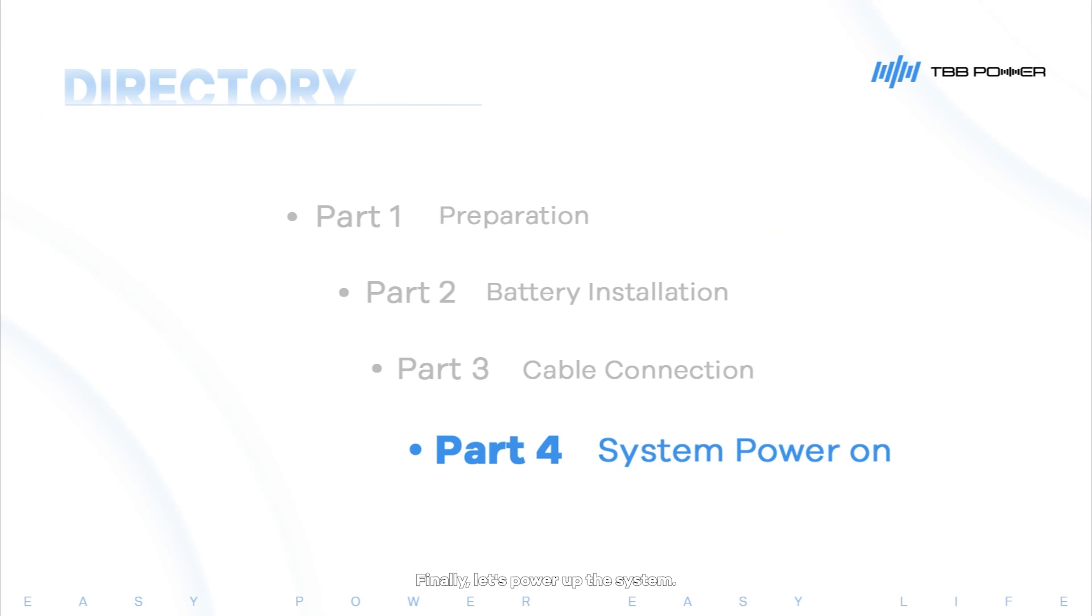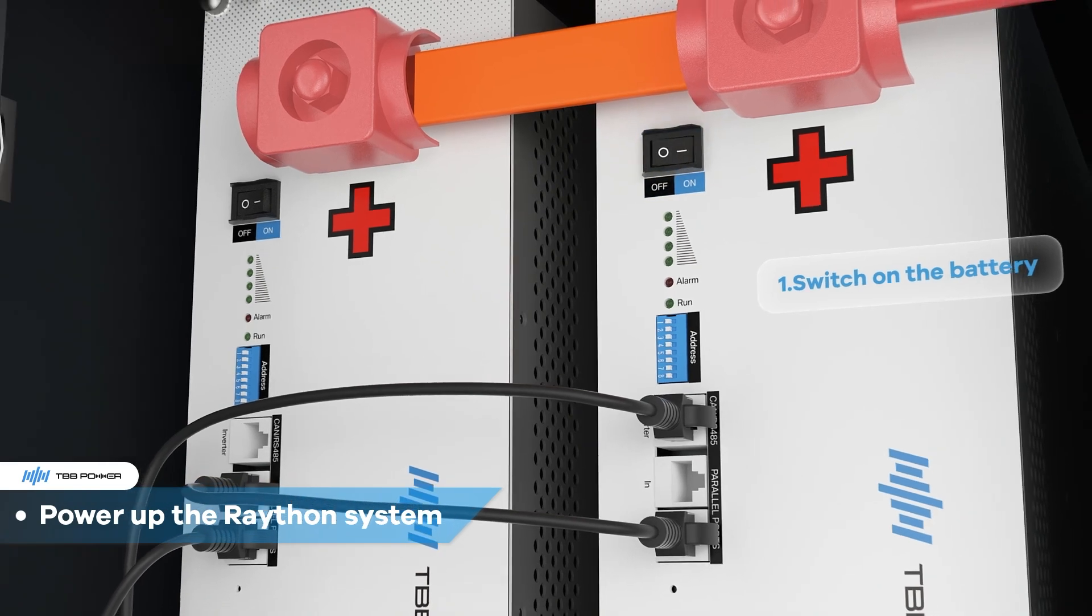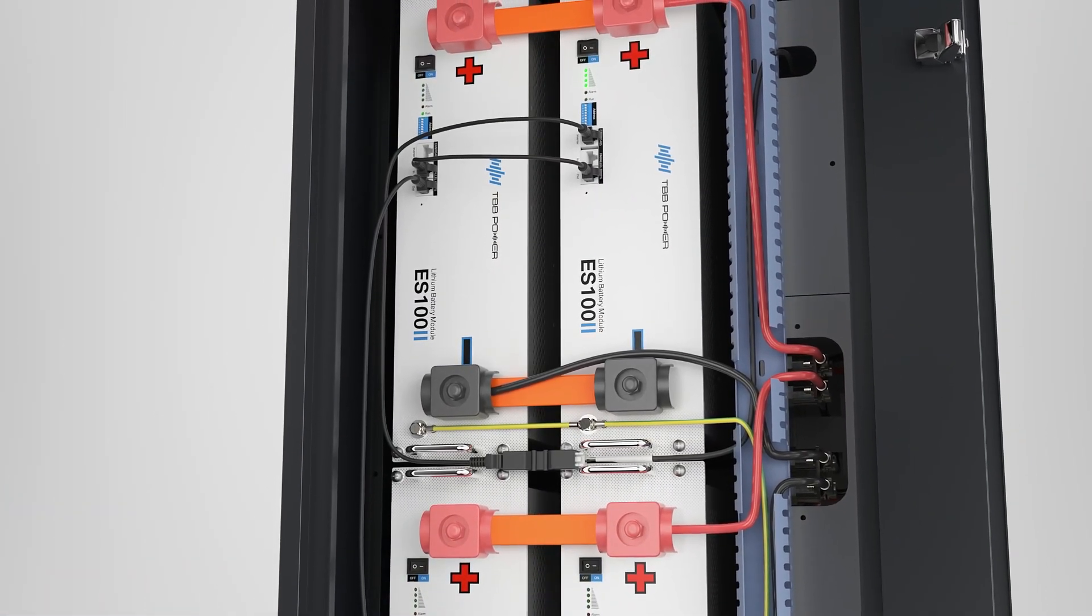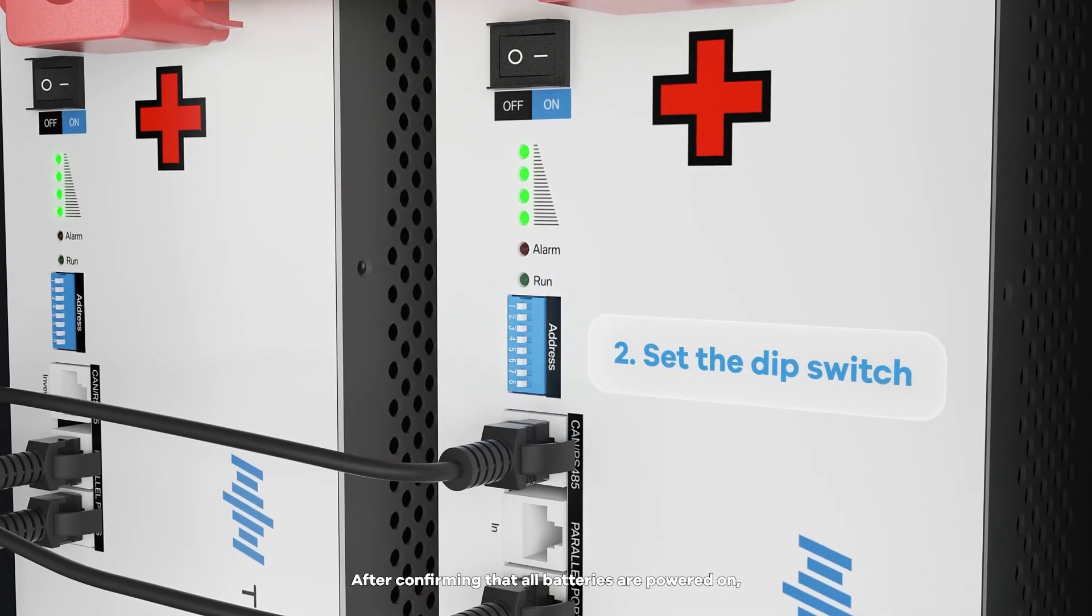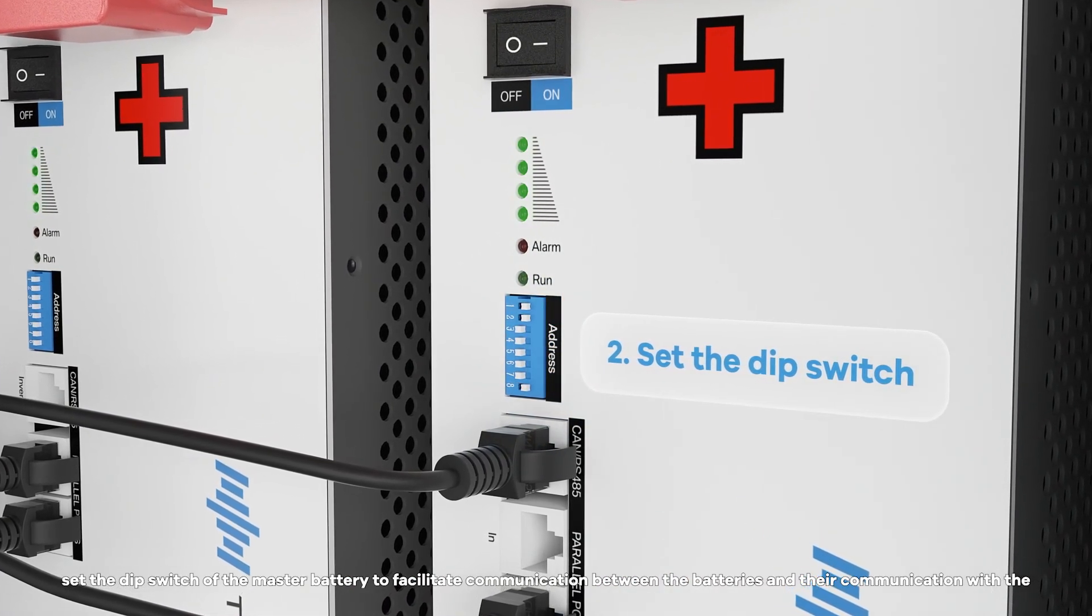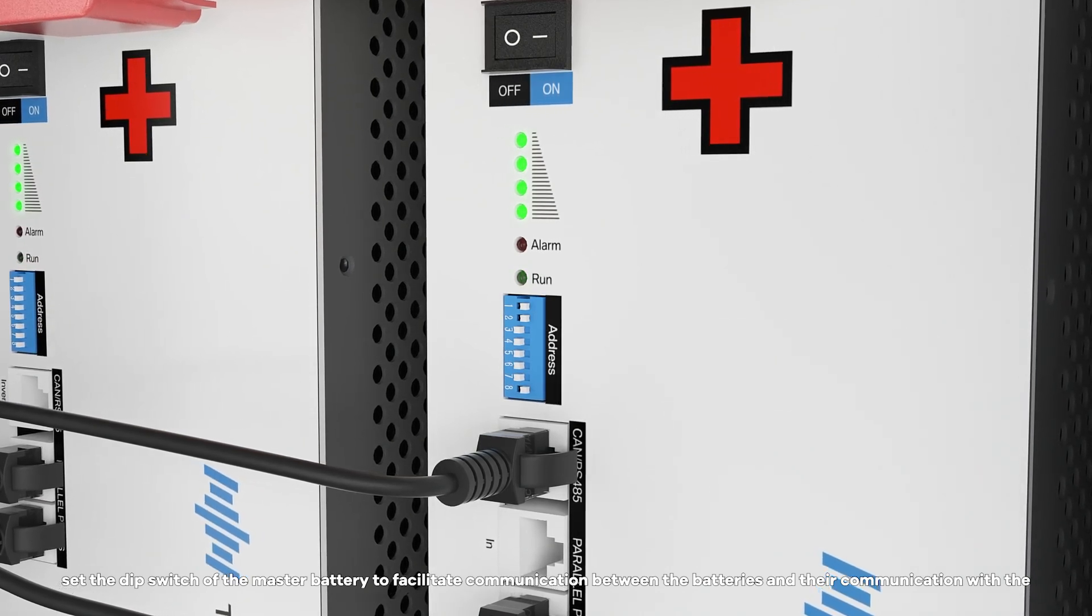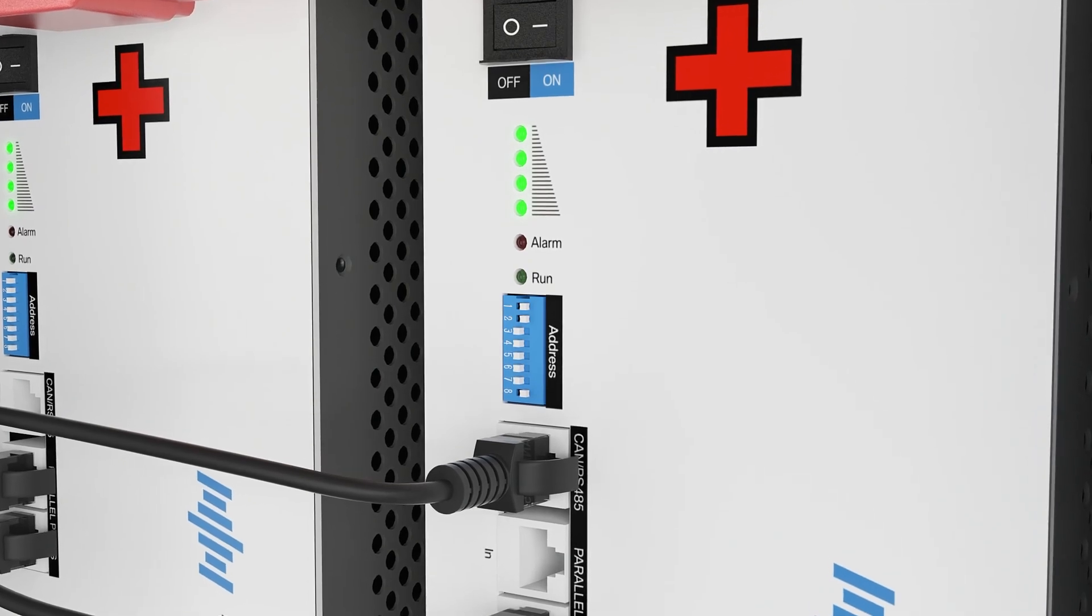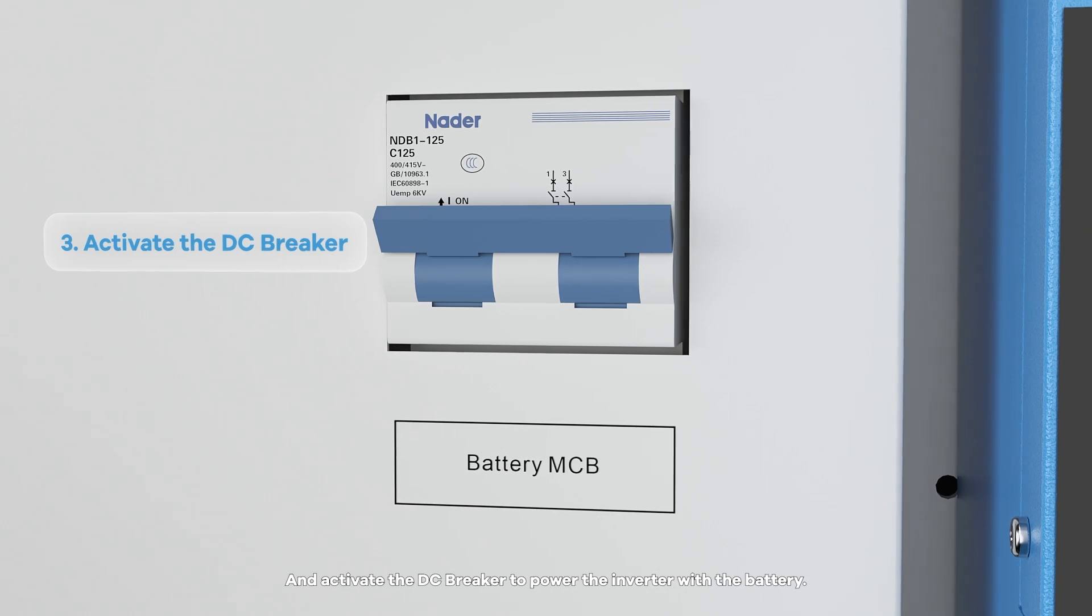Finally, let's power up the system. First, turn on the battery switch. After confirming that all batteries are powered on, set the DIP switch of the master battery to facilitate communication between the batteries and their communication with the inverter. And activate the DC breaker to power the inverter with the battery.